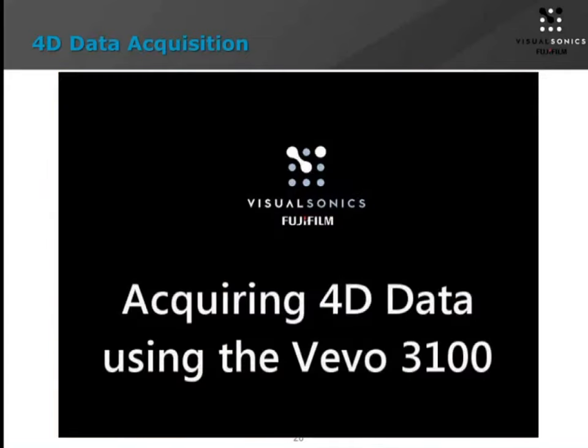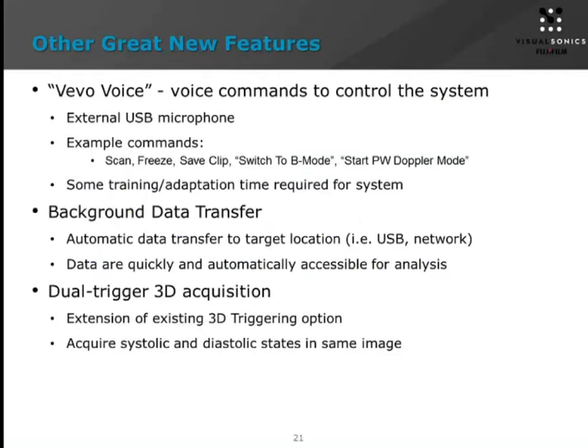Changing gears to some of the other new features — 4D is part of the second major software release for the 3100 platform, but there are other value-added features in this new release. One neat feature we've developed is what we're calling Vevo Voice — a voice command system to control the system. Example commands include scan, freeze, save clip, and switch to B mode. There is a little bit of training adaptation time required for the system to recognize patterns in your voice, but it is quite efficient, especially if you're doing any hand scanning where you're manually manipulating an animal with the transducer in the other hand. It really does help speed up throughput and gives you flexibility to quickly save images or switch to different modes while your hands are busy.